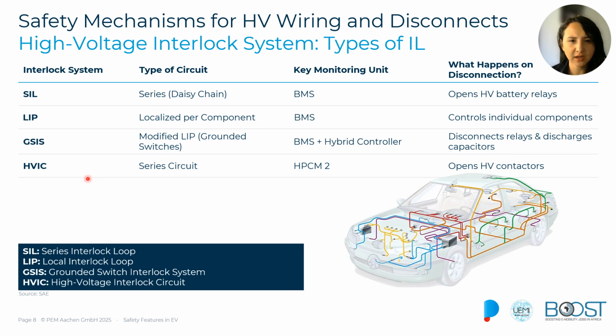And finally, we also have the high voltage interlock circuit, which is the one that we explained before. In this case, we have a series circuit type that is controlled by the high voltage powertrain control module. And in this case, we also will open the high voltage contactor if there is any failure.